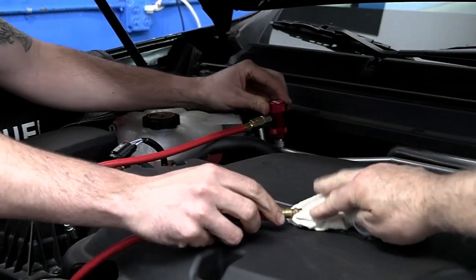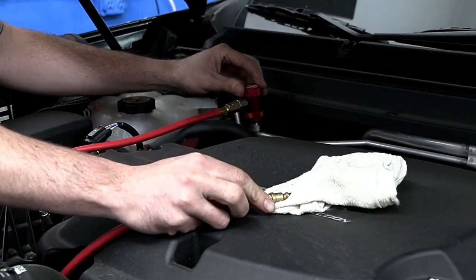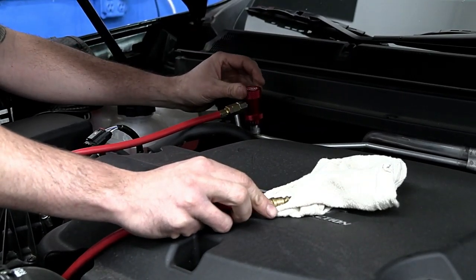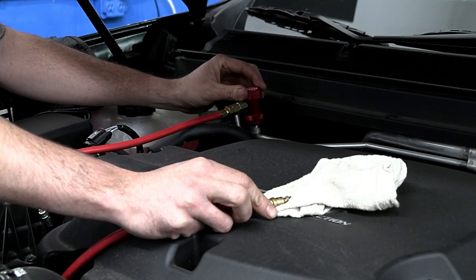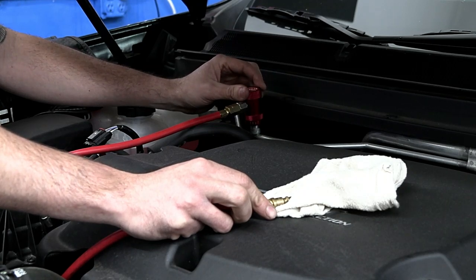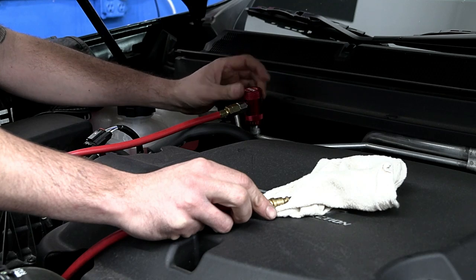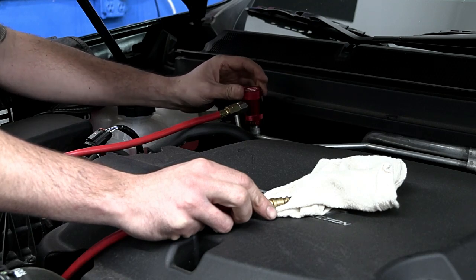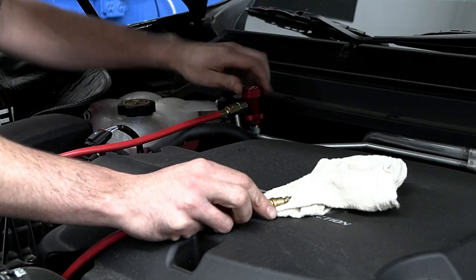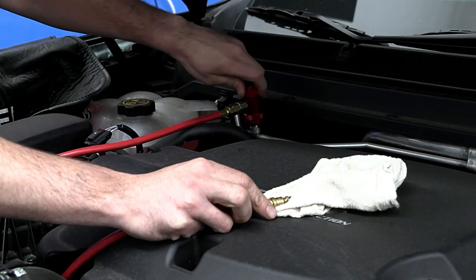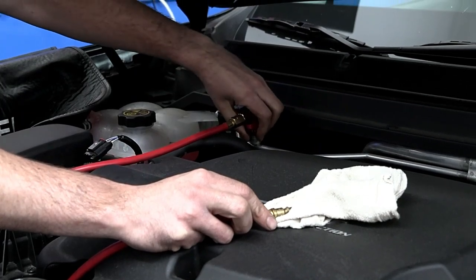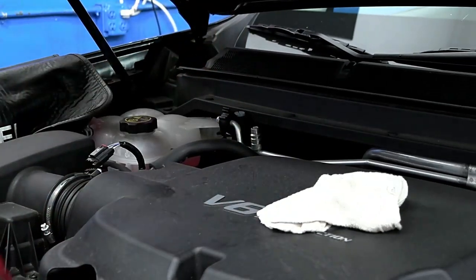Okay, so no oil is coming out. We're going to let all 200 PSI out. Once we let it out, we then put this into a vacuum. This is what we do because you can get messed up. And what do I mean messed up? There's going to be a mandatory leak check that is 10 minutes on vacuum on any machine you own. It is a federal law that it does that.